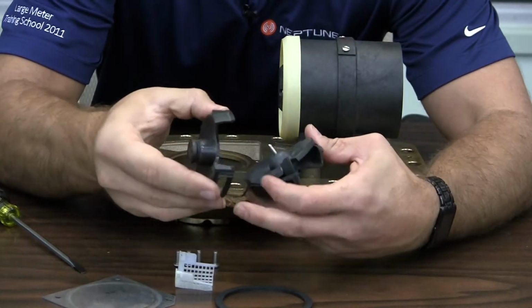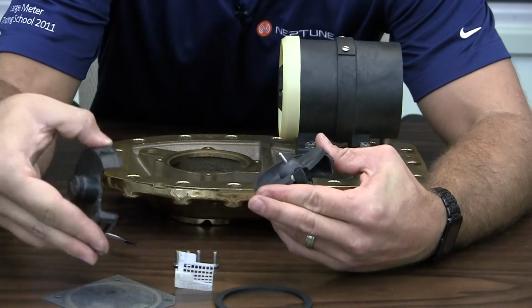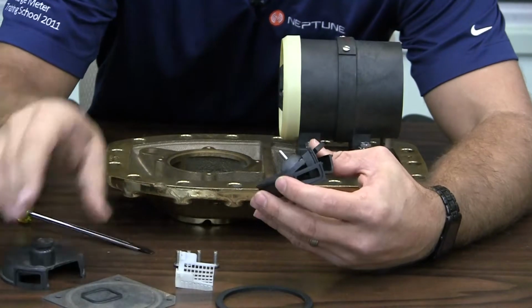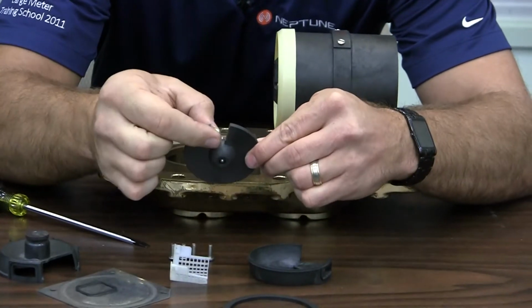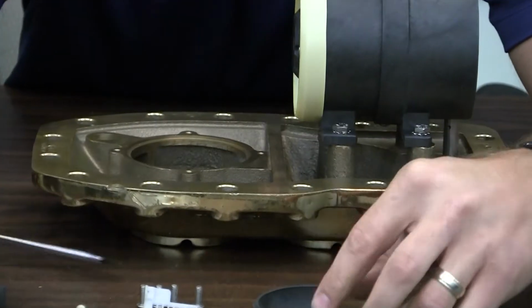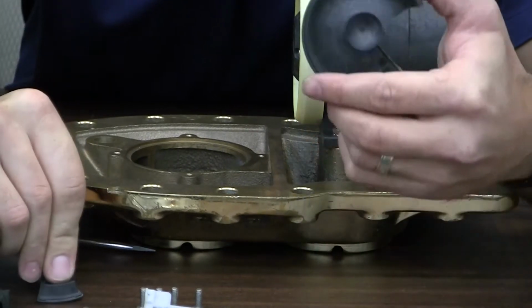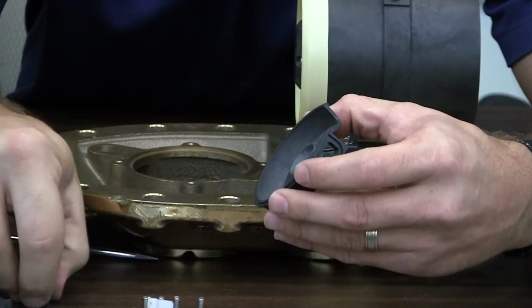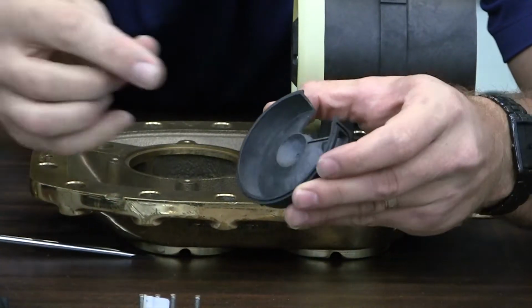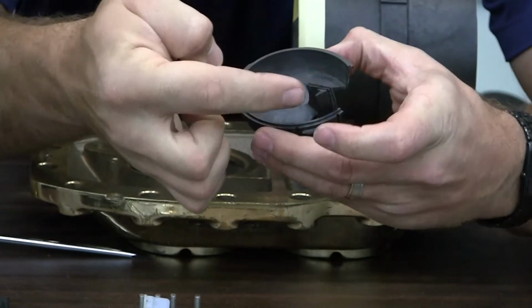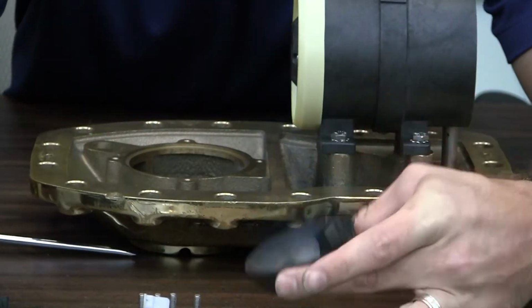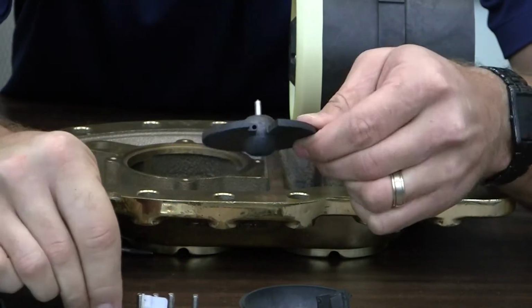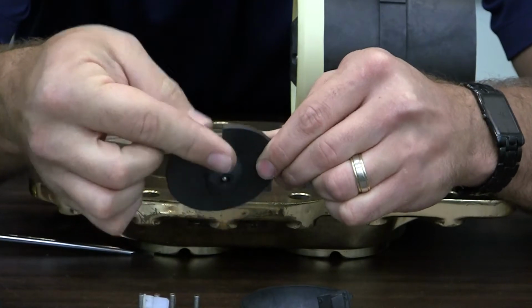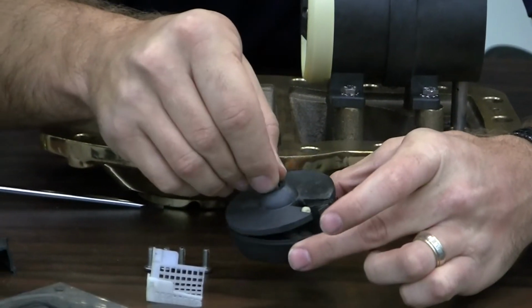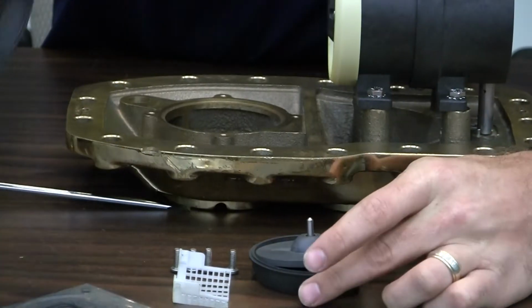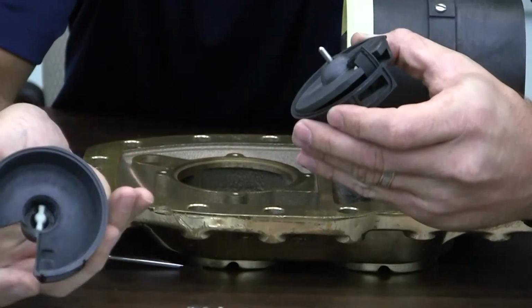The first component will be the gasket that forms the seal for the chamber, the upper chamber assembly, the ball and disc, which also houses the thrust roller, a diaphragm, and the lower chamber assembly. Now, to put this back together is pretty simple. You can see the slot on the lower chamber where the diaphragm rests. Just make sure you line with the wall of the diaphragm facing to where you can see a groove for the thrust roller. I'll take the ball and disc, I'll put the thrust roller in the hole that's machined in. Once you have these together, you can place it in the lower chamber. And then take your upper housing and slide it, and it has a mating groove for that diaphragm.